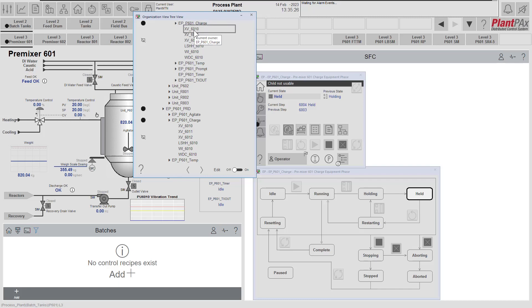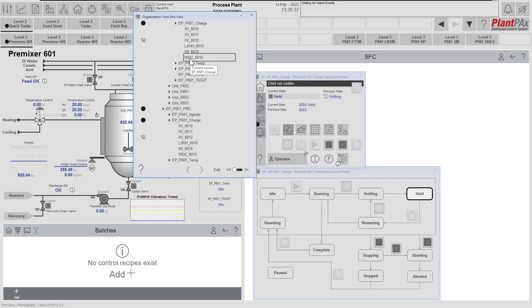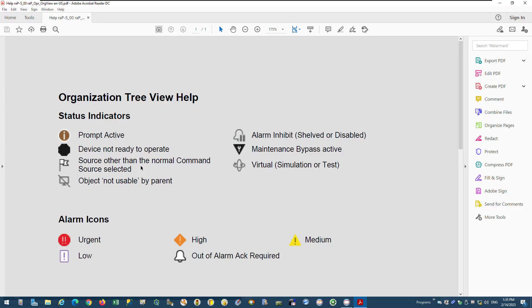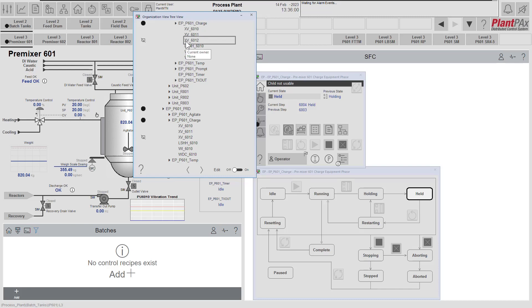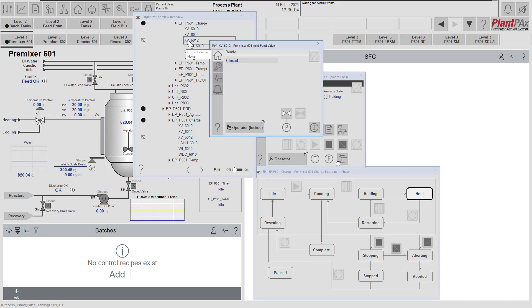The tree view shows three valves which charge different materials into the top of the tank, the high level switch for the tank, the current weight value for the tank, and the dosing controller used to dose a certain amount of weight into the tank. This view is showing us that device XV6010 has an issue. We can bring up the help to see what the symbols mean — this particular symbol means that the object is not usable by the parent. Clicking on this device brings up its faceplate so we can fully understand what the issue is.